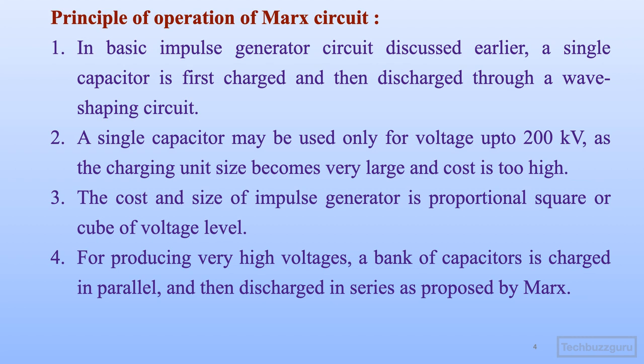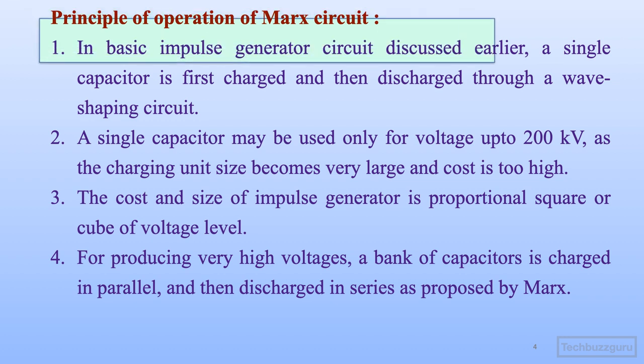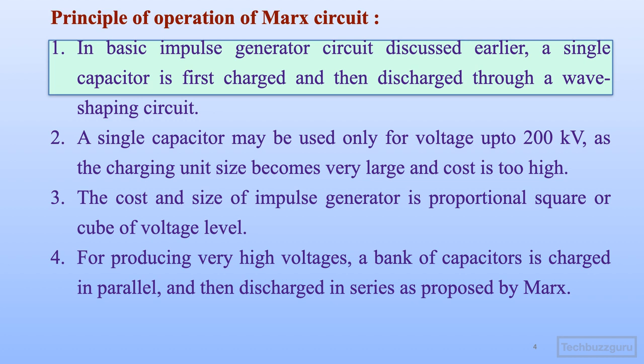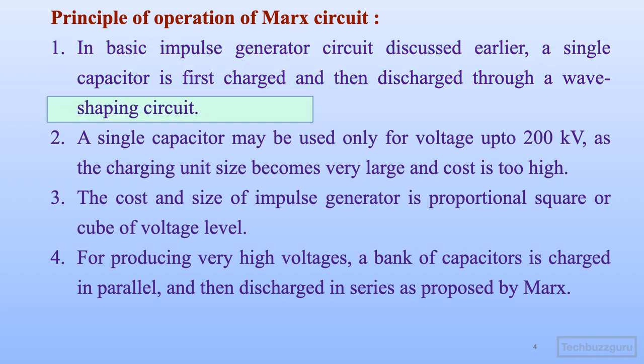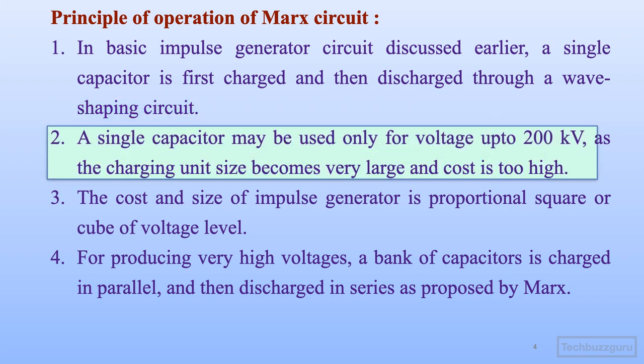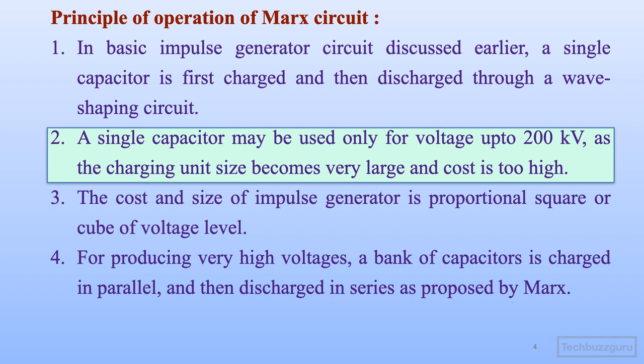We'll first take up the principle of operation of the Marx circuit. Before we move to the multi-stage impulse generator, let us recollect that in the basic impulse generator circuit discussed earlier, usually a single capacitor is first charged and then discharged through a wave shaping circuit. Such a circuit with a single capacitor is suitable only for voltages up to 200 kV, as the charging unit size becomes very large and cost is also too high for higher voltage levels.